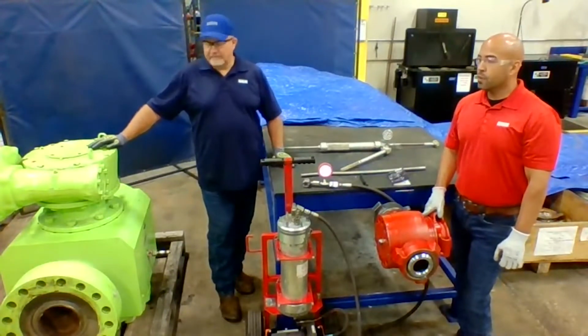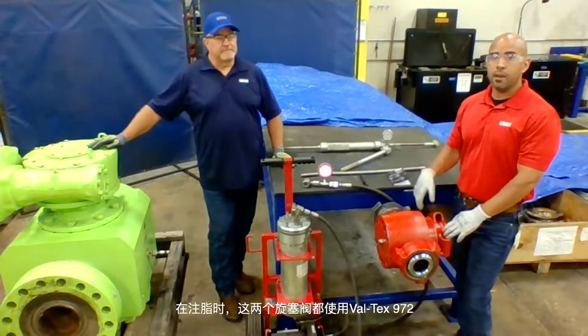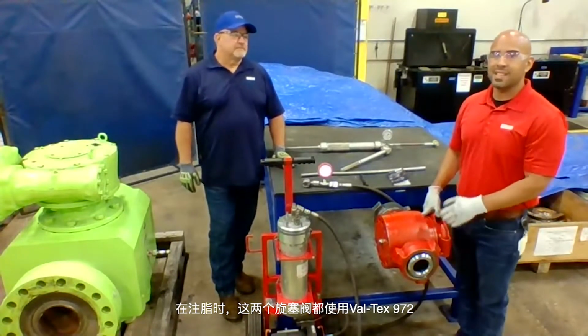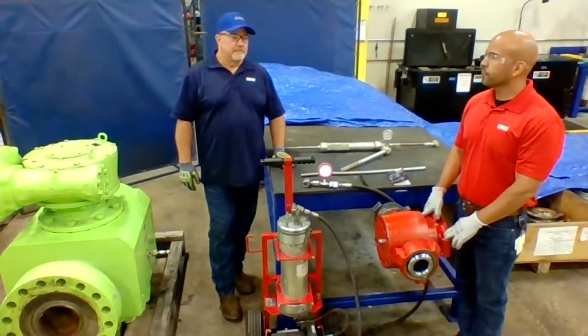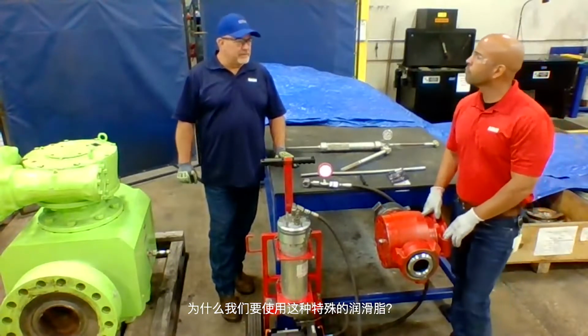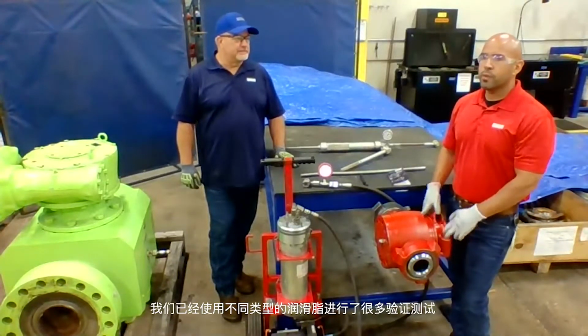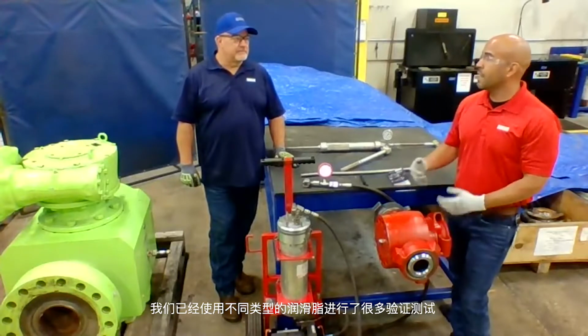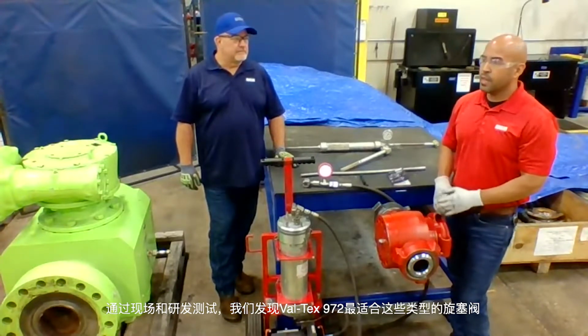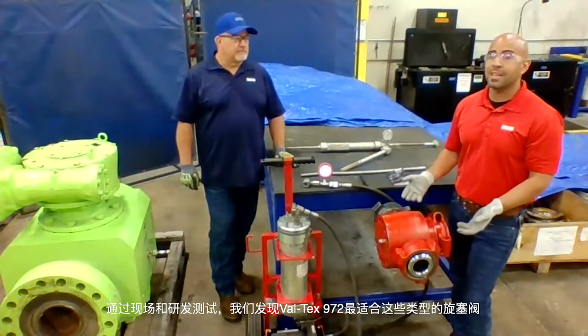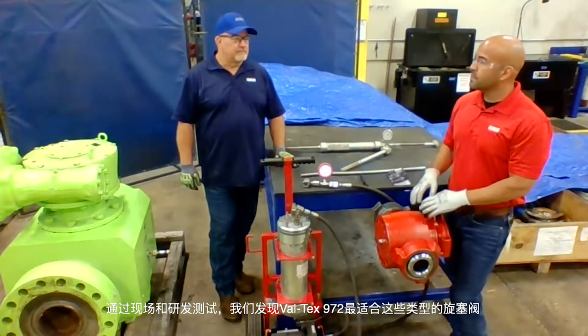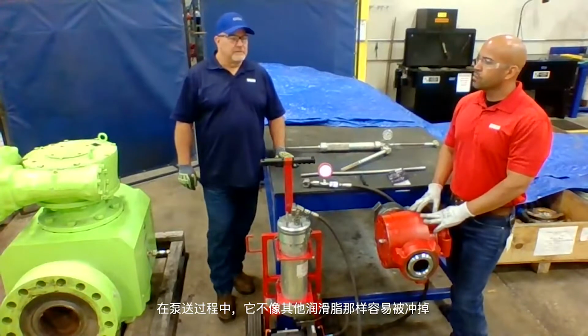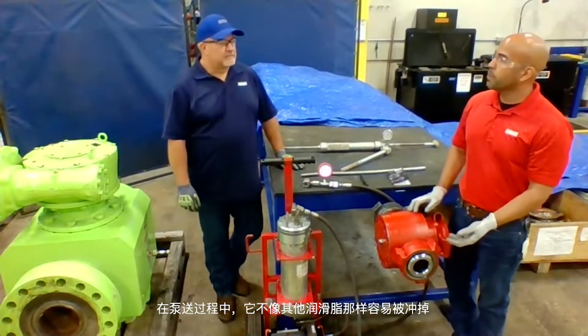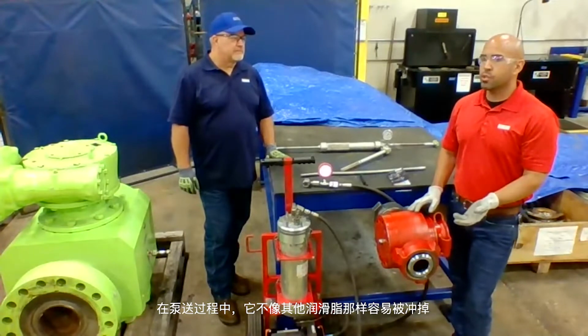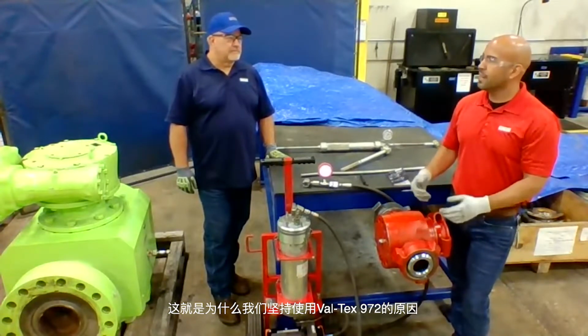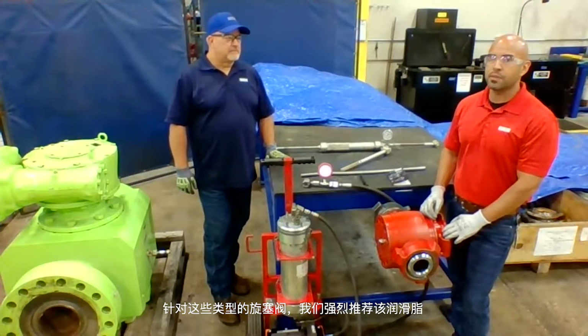These two plug valves do take Val-Tex 972 when it comes to greasing. And why would we use that particular grease? Well, what's different about it? We've conducted a lot of validation testing with different types of grease. Through field and research and development testing, we found that the Val-Tex 972 works best for these types of plug valves. It doesn't easily get washed out during the pumping process like other greases do. So that's why we say stick to the Val-Tex 972. It's fully recommended for these types of plug valves.